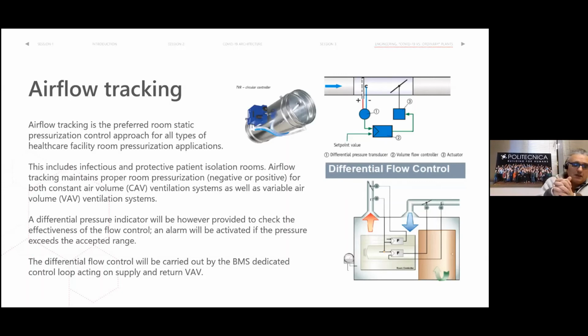The way to do it is, during the commissioning phase, you have to check exactly what is the proper flow rate, supply and return, to provide the proper pressure. And then, checking that, you can provide the pressure in an indirect way. So you have to control the flow to control the pressure, because it's more precise to control the flow in a VAV system, where the flow is measured very precisely, than to control directly the pressure. Of course, you have to provide a differential pressure indicator to check if it works correctly, but it is not utilized for the adjustment. It is just utilized for indication. This is called airflow tracking, and is always utilized in this way.